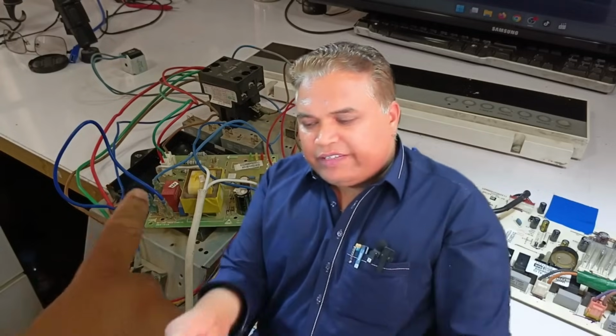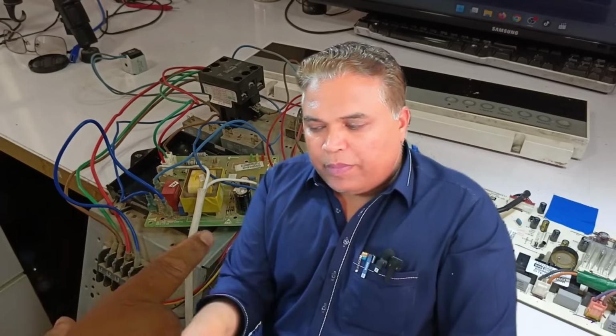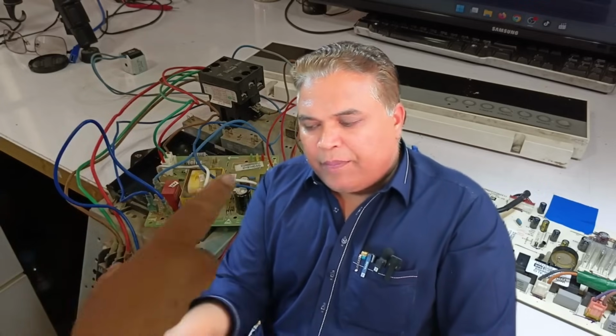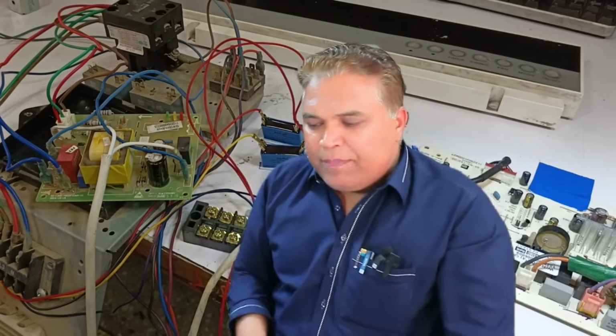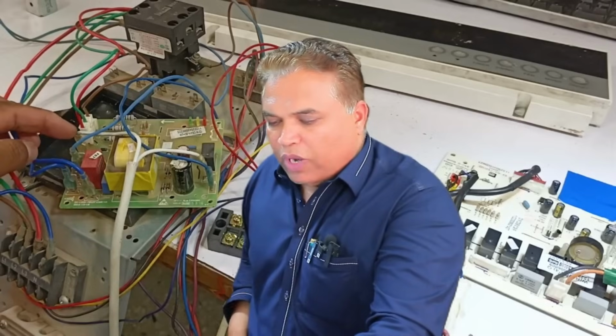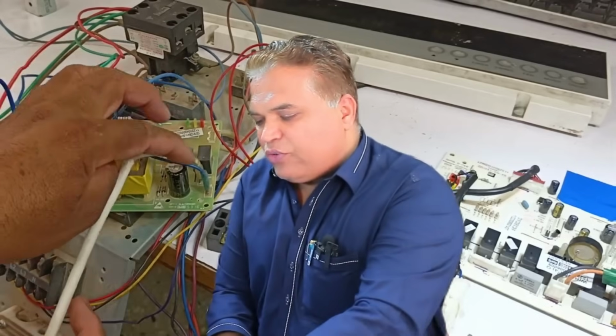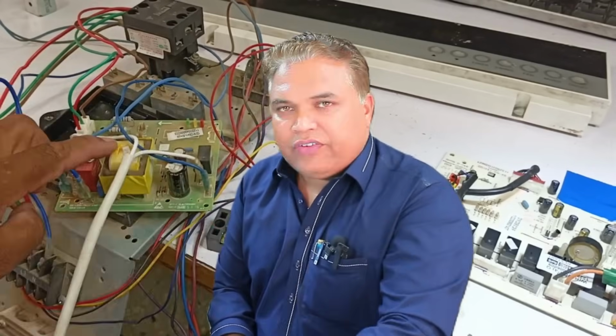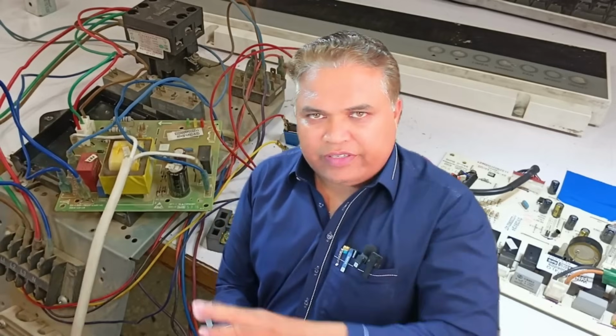Now I will show you which fault is occurring in this PCB. The phase detection circuit is working perfectly fine. There is no issue with it because the 3-phase supply that I generated is functioning correctly. I also checked the high-pressure switch on site, and it showed continuity, so it is confirmed to be working properly. Now, the real problem is that the signal from the outdoor unit is not reaching the indoor unit, which is why this issue is happening. We will now try to find out why the signal is not coming through.